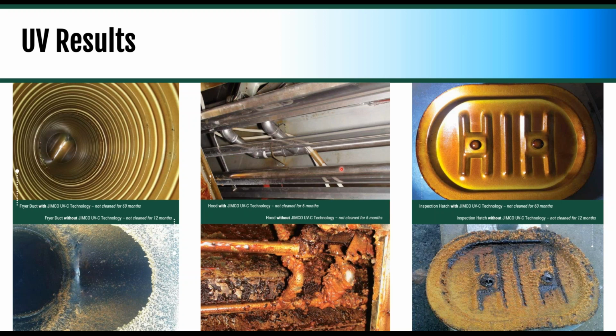This is the hood cavity. This is actually the same time frames here, so that's 6 months and 6 months. But as you can see, the difference is totally night and day. It really is amazing. And we went and actually toured the facility here. They had a heat exchanger in the unit where we looked, and they're changing the HEPA filter in the heat exchanger every 3 years. Whereas if they didn't have the UV system, I would assume that they would be changing it monthly, if not sooner, because grease really clogs those HEPA filters pretty quickly.